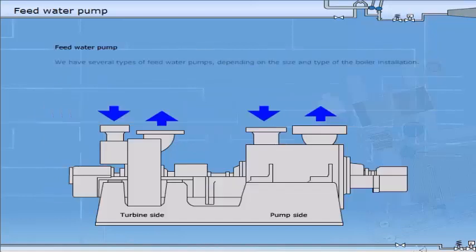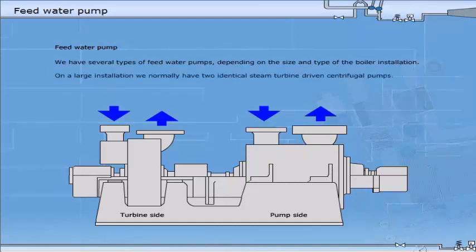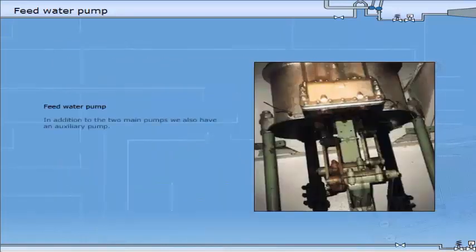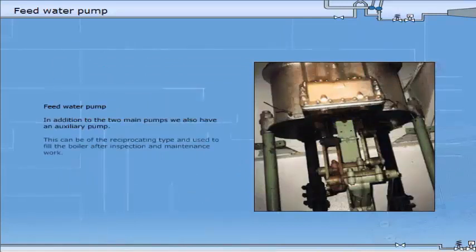We have several types of feed water pumps, depending on the size and type of the boiler installation. On a large installation, we normally have two identical steam turbine driven centrifugal pumps. Each of the pumps has a capacity well above the total boiler capacity. In addition to the two main pumps, we also have an auxiliary pump. This can be of the reciprocating type and used to fill the boiler after inspection and maintenance work.